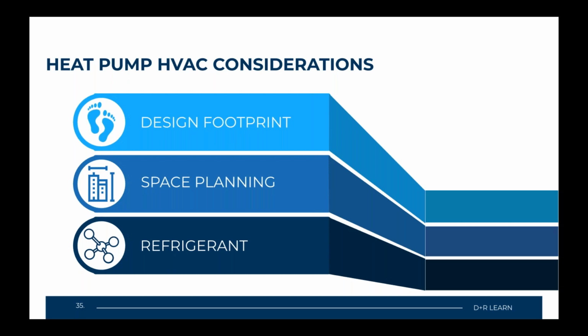That is your design footprint, your space planning, and also the type of refrigerant that you'll be using. The footprint is just the clearance and location of the outdoor system. Space planning is planning ahead for distances and heights needed for different components as far as installation, operation, and maintenance. Refrigerant is part of the safety and code requirement, with a lot to do with ASHRAE codes 15 and 34, which we'll look at more closely.